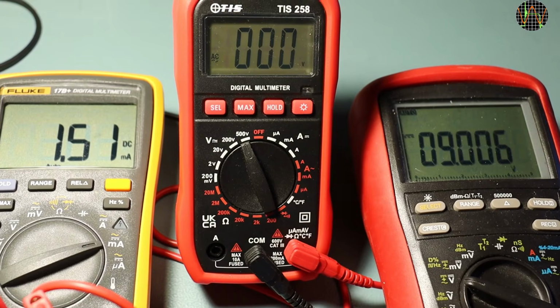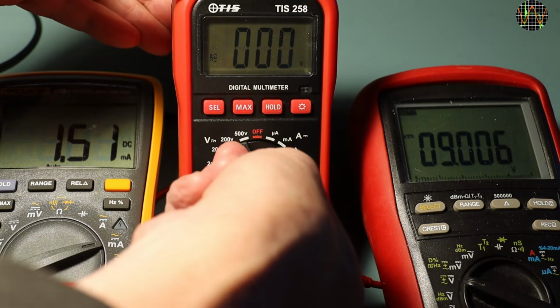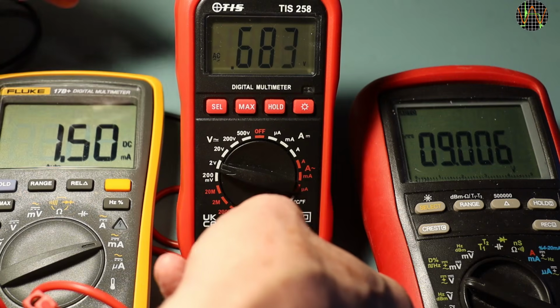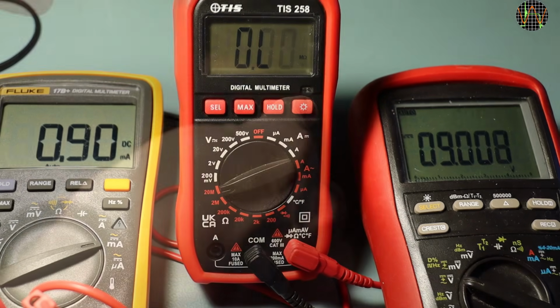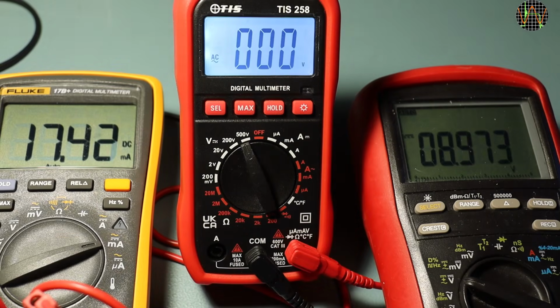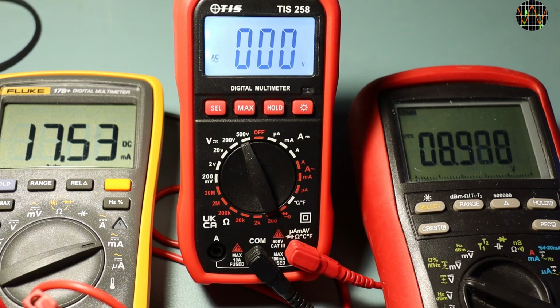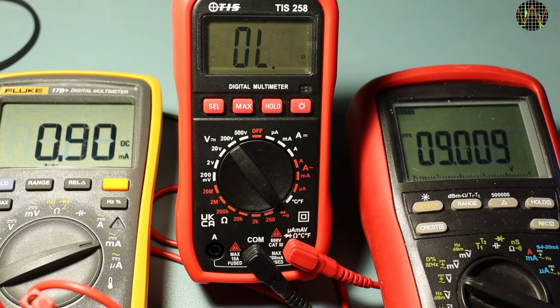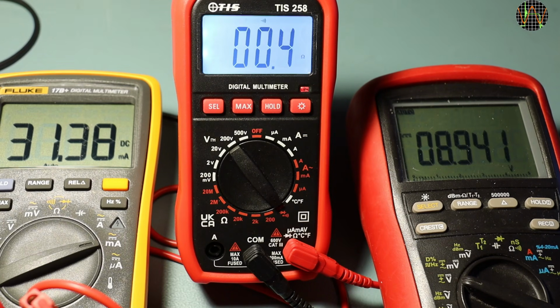To finish the review off, the battery draw is quite low. Just 1.5 milliamps for all modes except resistance, needing only 0.9 milliamps. Comparatively, at over 17 milliamps, the backlight draws a lot, and the continuity beeper also uses 15 milliamps. Beeping while backlight is on draws more than 31 milliamps, so best avoided.